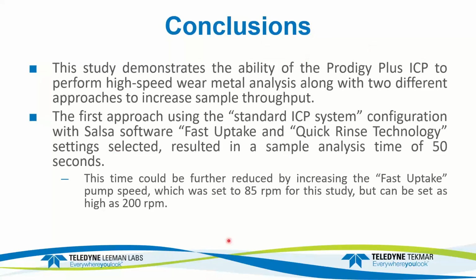So in conclusion, this study shows that we can use the Prodigy Plus to perform high-speed wear metal analysis at relatively high sample throughputs. In the first approach, we use basically the standard ICP configuration with Salsa software, and we modify the software so that we increase the pump speed during the uptake, fast uptake, and we use the rinse technology, which goes to the rinse while the sample's being analyzed. So we're rinsing and running samples at exactly the same time. We could go a little bit faster if we wanted to. We only set it to 85 RPM, but can go as high as 200 RPM. That can bring the sample uptake down to a really short period of time, maybe even 10 seconds or so. Again, the goal was to be less than a minute, so we didn't really explore how much lower we could go.